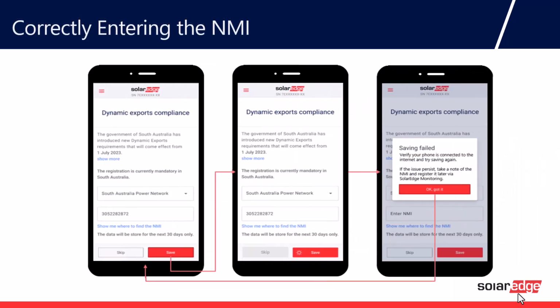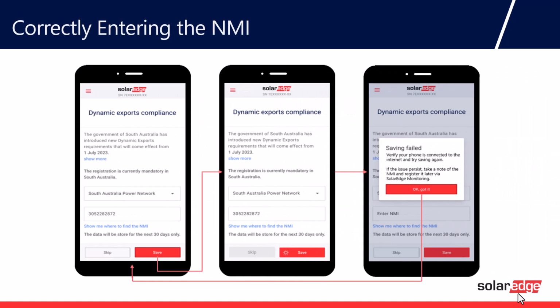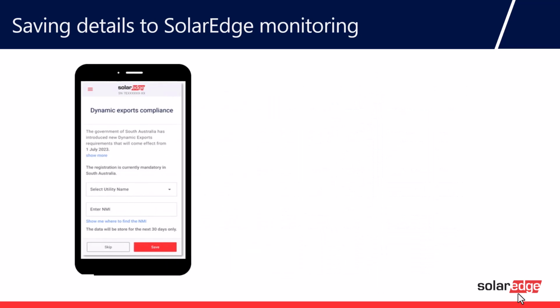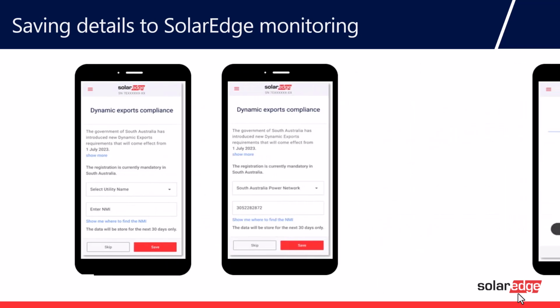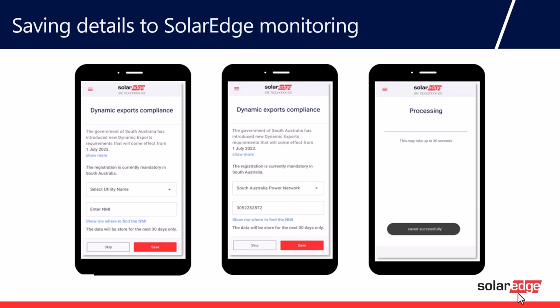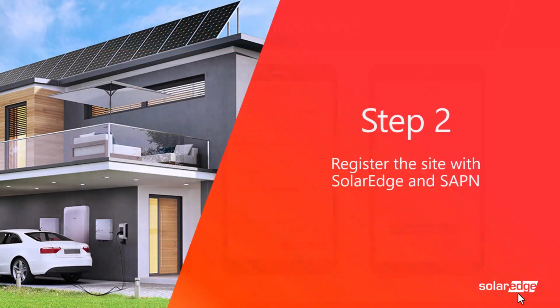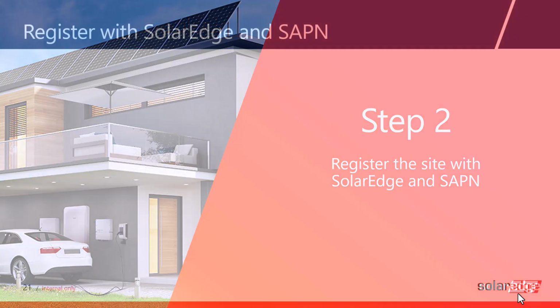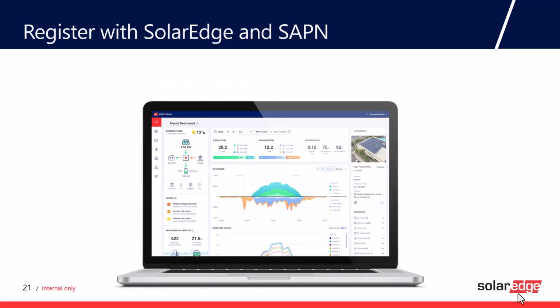What it allows you to do is, once you select South Australia Power Networks, enter an NMI number, and it will check that the NMI is in the correct format, with the correct number of digits. What's important is that the number is recorded, because as part of the commissioning process, you need to enter the NMI number into the monitoring platform. Once you've gone through those stages, you can go ahead and process the normal commissioning stages of the inverter as normal. Step 2 is then to register the inverter with SAPN, and like I said before, this is done through the SolarEdge monitoring portal.